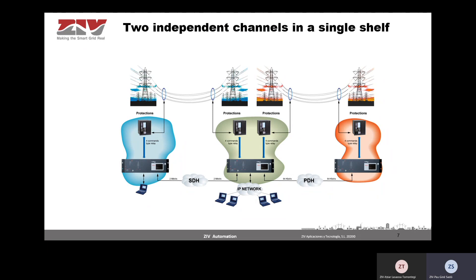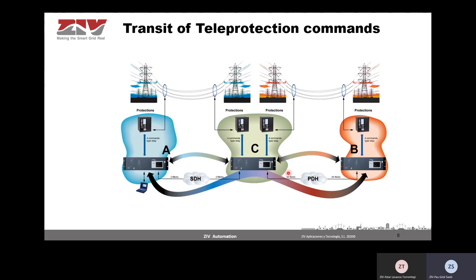The next example is two independent teleprotection terminals in a single shelf. Here, in the substation in the middle, we can see one TPU device equipped with two communication interfaces. In that case, this device is acting as two independent teleprotection units — a very cost-effective solution, because you only use one teleprotection device instead of two, and you are able to communicate to both the substation on the left and the substation on the right. It is also possible to equip this unit with a redundant power supply.